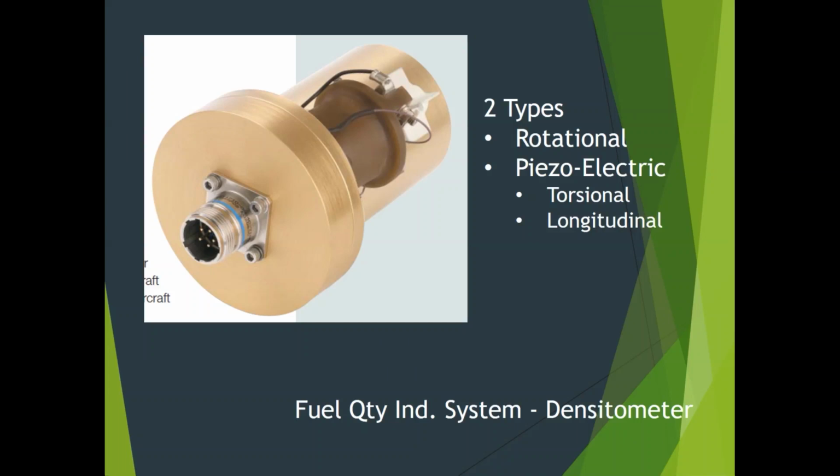And the thicker the fluid, the more it's going to slow down that vibration. And so that return frequency may be different. And these typically are in the ultrasonic range. They're above 20,000 hertz, like 20 kilohertz. So say the input frequency is 30 kilohertz, 30,000 hertz. It vibrates 30,000 times a second.